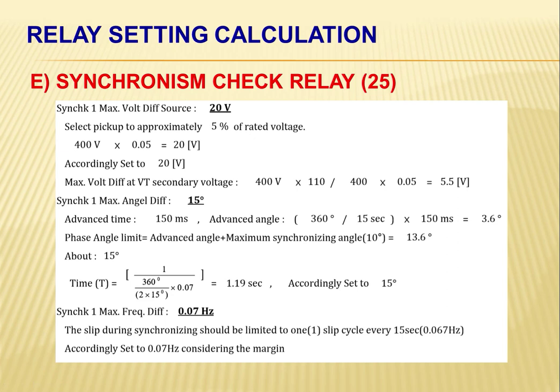Next, here we have the synchro check relay, or the ANSI 25 relay. As discussed earlier, there are instances that both buses, bus A and bus B, or source 1 and source 2, will be connected in parallel. For 2 power sources to be synchronized, the following conditions must be matched. First, voltage. Second, the phase rotation. Third, the phase shift. And fourth, the frequency.